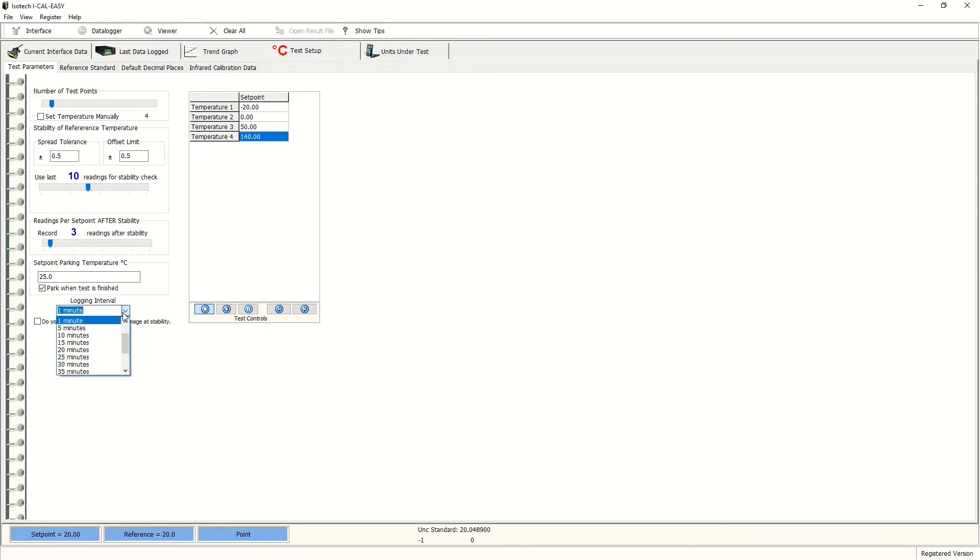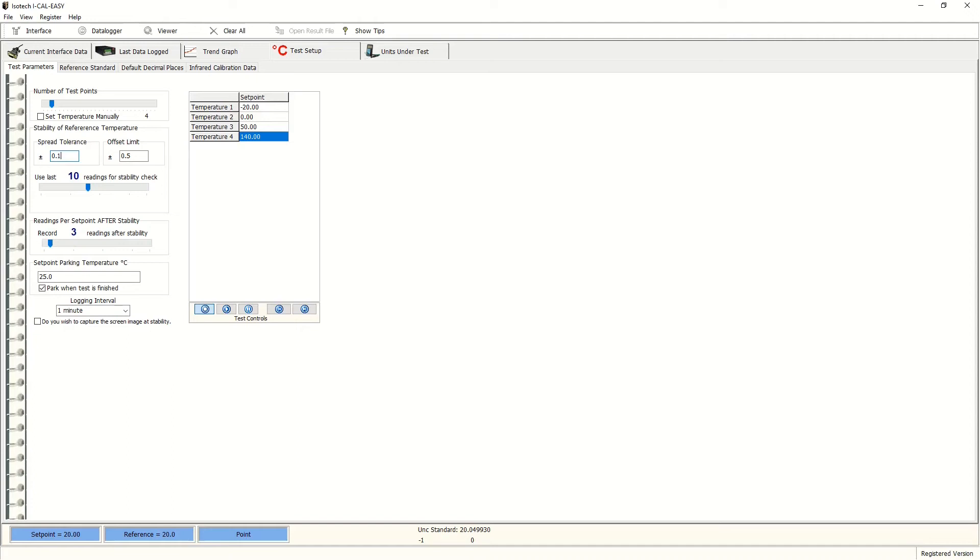So we'll bring that down to 25 and also the logging interval. We'll choose one minute. Now we can input tolerances where we can say we have stability in the dry block. So these can be adjusted to make the decision on whether to take readings as a result.